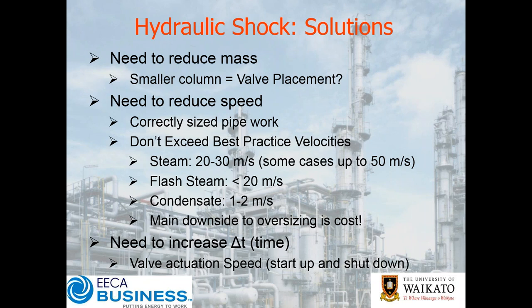An important thought to keep repeating as a mantra: when you size your condensate system pipe work, you obviously size it based on the expected duty. But think about what happens when something upstream fails — what is then in that pipe work and what will be the consequence? You might think, well, if a steam trap fails I'll fix it. For those of you running a factory, plant needs to keep running — they're not going to stop everything just so you can have a window to fix a steam trap. So you need to think about how much resilience your system needs, based on how many steam traps could potentially fail before you're able to have a window to fix them.